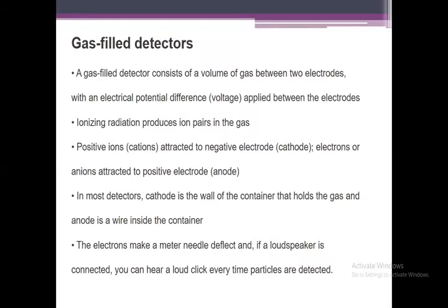The Geiger-Müller counter is also a form of gas-filled detector. Gas-filled detectors have different regions. The first region is the ionization chamber, the second is the proportional counter, and the third region is the Geiger-Müller counter. A gas-filled detector consists of a volume of gas between two electrodes with an electrical potential difference applied between them. Ionizing radiation produces ion pairs in the gas.